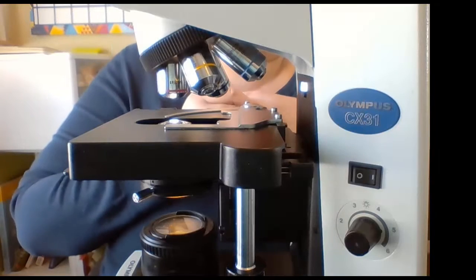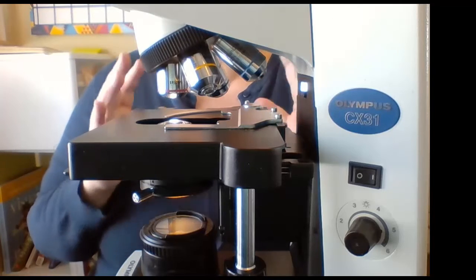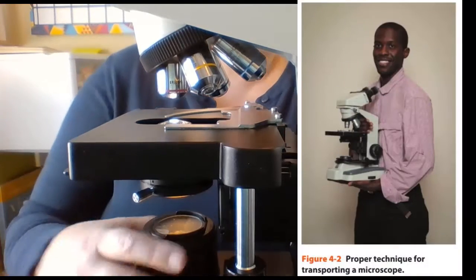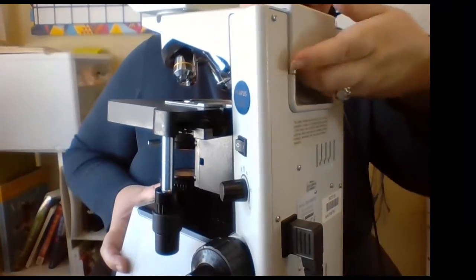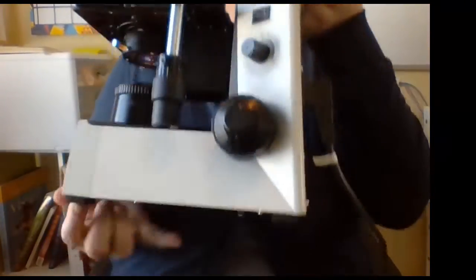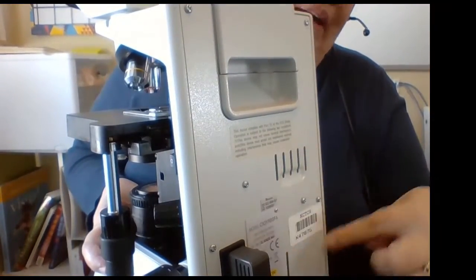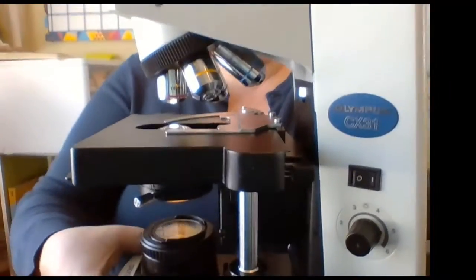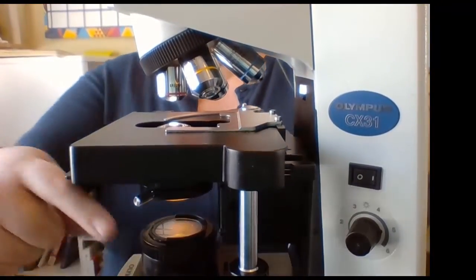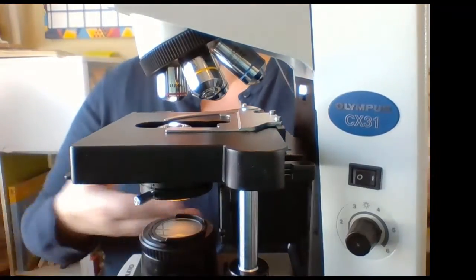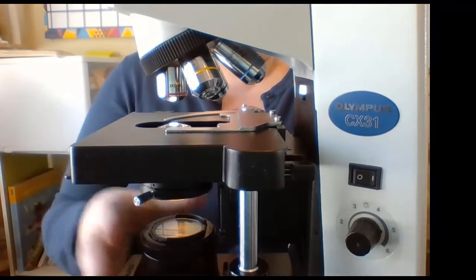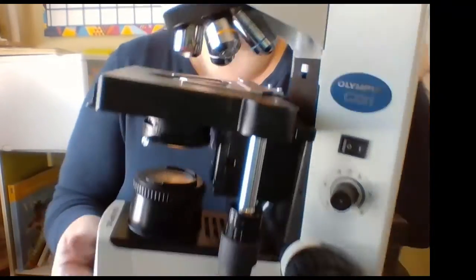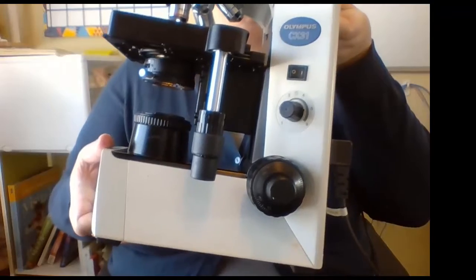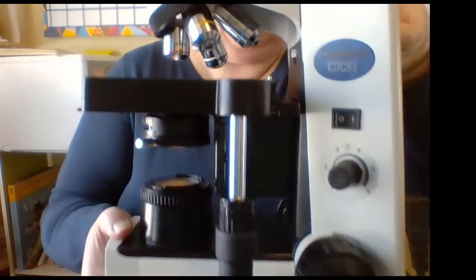So the first thing we often demonstrate in a face-to-face class with the microscope is the appropriate way to hold and carry the microscope. This Olympus microscope has a handle on the back where you can put one hand, and then the other hand always goes underneath the base. This particular microscope does not have any cord management system in the back. So when you get this out of the microscope cabinet, it usually has the cord wrapped around the base in some way. You would keep it wrapped to carry the microscope because you don't want it dragging and you don't want to trip over it while you're carrying the microscope.